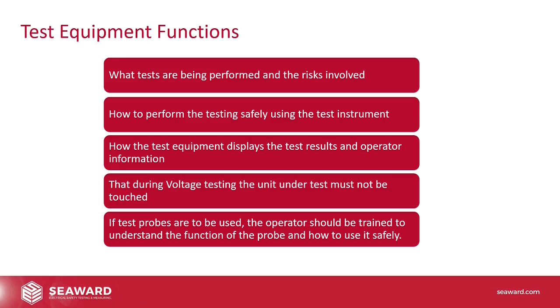The test equipment will display the test results in different ways. So there are loads and loads of different testers out there on the market. They'll all communicate with the operator differently. It's important that they know how it's displayed and what other information it's giving the operator. So a lot of our testers will give a pass or a fail result, but it might be that the tester your operator is using just gives a value back, and the operator has to evaluate and decide if it's a pass or a fail. So really important training consideration there.